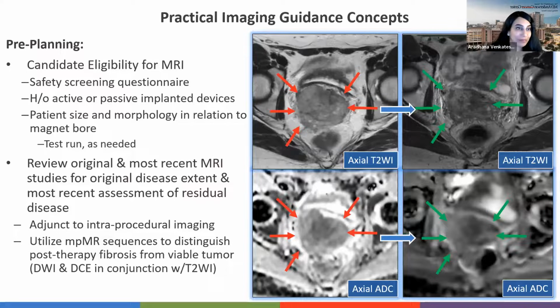Sounds good, thank you. So what are some practical image guidance concepts just prior to performing your procedure and on treatment day? Number one is your candidate's eligibility for MRI, as mentioned, with respect to MR safety considerations, also patient size and morphology. We perform these procedures in a 70-centimeter wide bore magnet that has a 500-pound maximum weight capacity on the table. But not all patients who are near that weight limit may in fact fit into your 70-centimeter bore. It depends on their body habitus and distribution of fat. So if there are questionable cases, it's not unhelpful, in some cases, to have the patients have a test run on the MR tabletop.